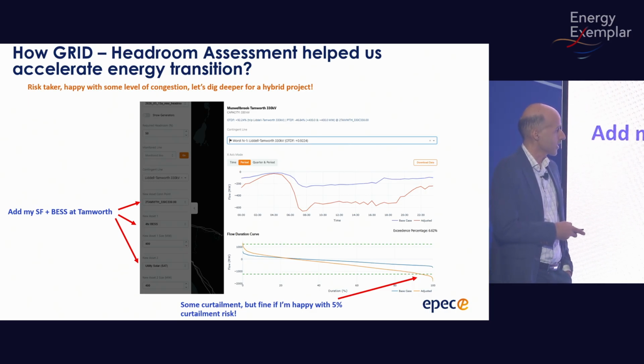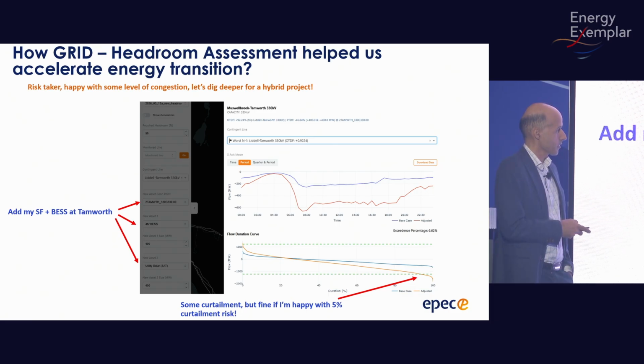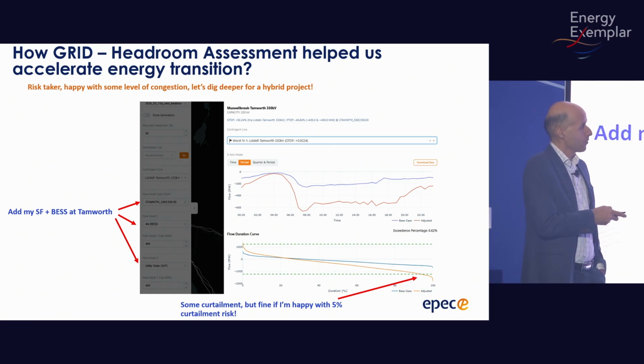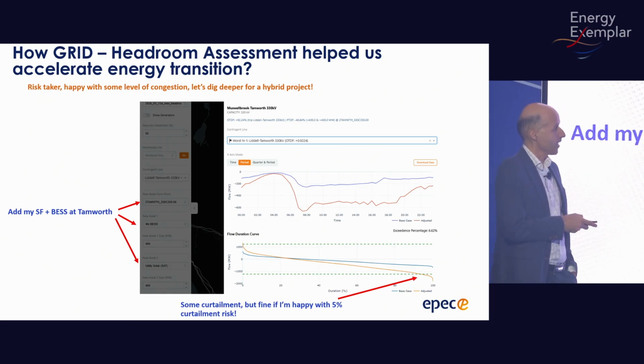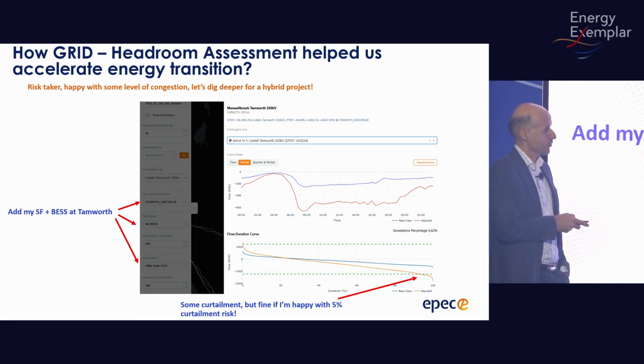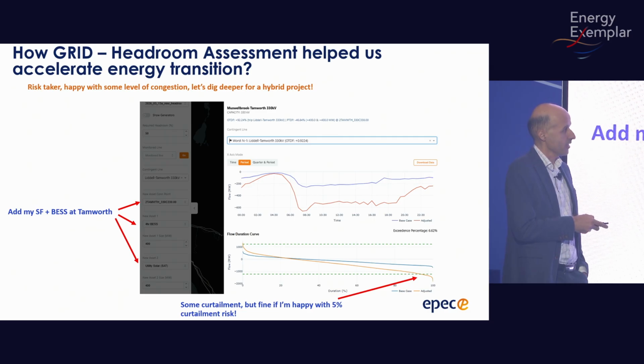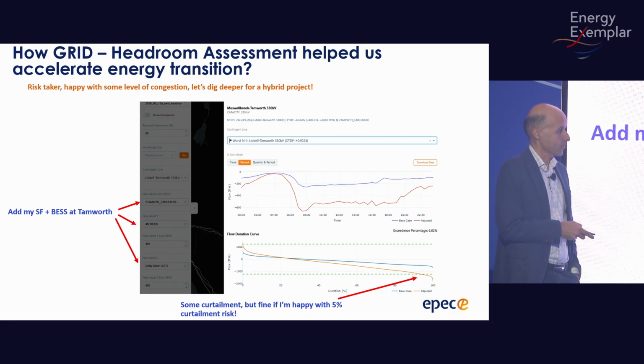For example, in this case I had a 4-hour, 400 megawatt battery, a hybrid project, plus a 4-hour, 400 megawatt solar farm. My line flow is updated now, so it's pretty much flat during the day and evening, because I still charge during the day and discharge in the evening, and my solar is generating. But what I see in the duration curve now is that I'm exceeding the line limits.